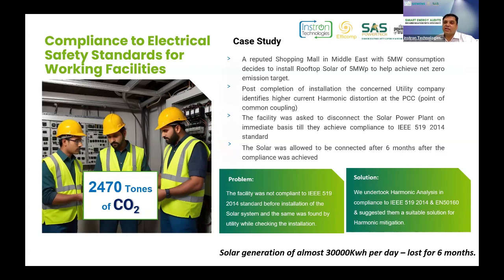They identified higher harmonic distortion at the point of coupling. On the day of the inauguration, they were asked to disconnect the solar power plant immediately, and they were asked to first achieve compliance to IEEE 519 2014 standard for harmonic compliance. The solar was allowed to be connected only after 6 months, once this compliance was achieved, because the client involved us for assessment, then solution designing, then the complexities.